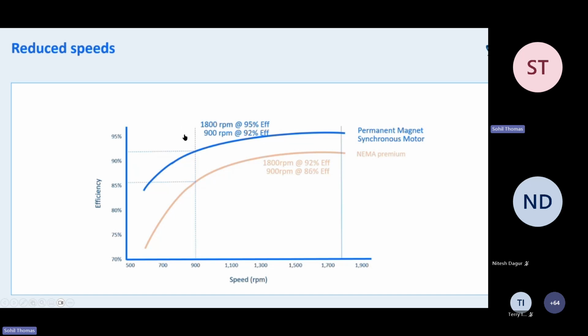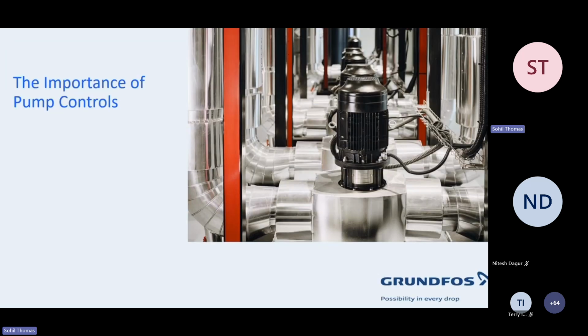But at nominal loads, which is where the pumps would be operating the majority of the time, at part loads, that's where this becomes highly efficient. You can see that it runs at 86% efficiency with NEMA Premium, whereas Grundfos motors go to about 92% efficiency. So that's why it's always important to make sure that we have the highest efficiency motor available in the market, to make sure you get the most savings when you go for it.